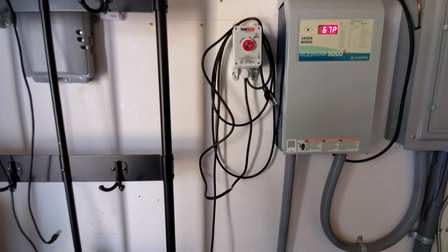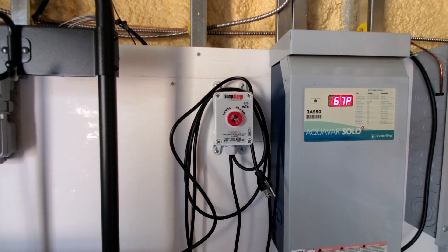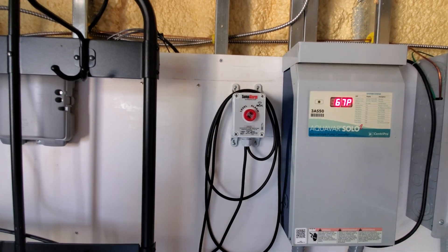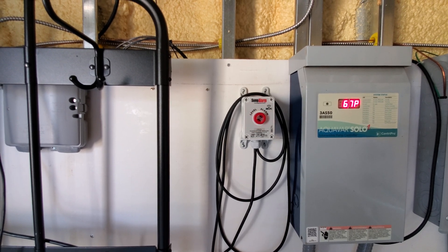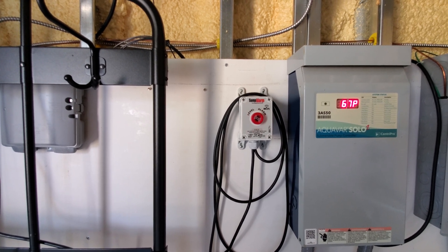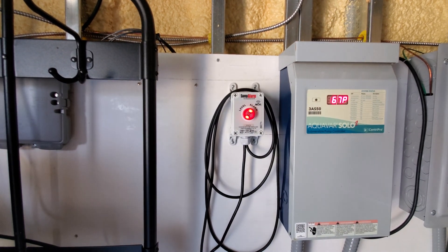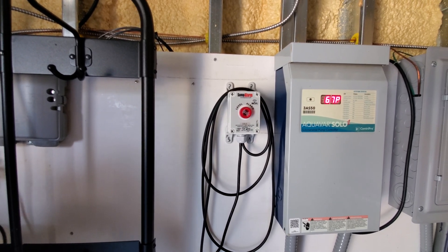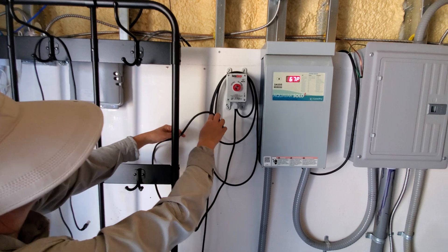One more thing — the sump alarm runs through that conduit connected to the tank and makes its way in here. We'll plug it in so you can see how it works. That chirp was it first powering on, and then it decided something is wrong — it's telling us the tank is low, which as we just saw inside, it is low, so it should be alarming. When it's full, the float valve will shut off the water flow and this alarm will stop. That's it for this video — we'll see you next time.